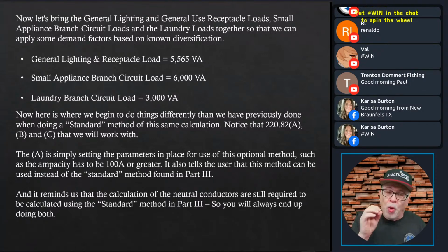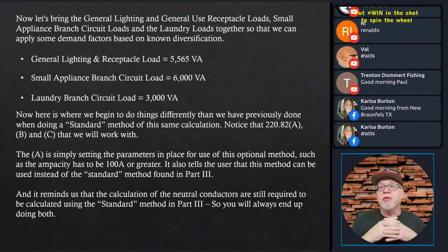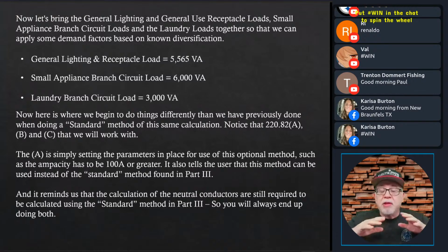But it's still important that you understand, because some of you may be running individual conductors and you do have to size it. Now, one thing you could do is say, I'm never going to make my neutral in a residential smaller than 2 times the size of my ungrounded hots in my calculation. As a rule of thumb, you'd probably be okay, right? But I think it's imperative you know how to do it. And on an exam, you've got to know how to do it. Okay?